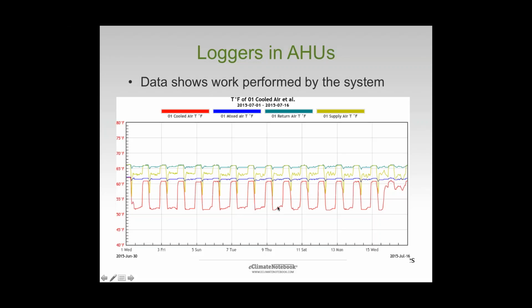Finally, after the air gets cooled down to this condition of 52 degrees, we send it out and it hits a heating coil. And before we send it out to the space, we find out that it's going to get heated back up to about, give or take, 64, 65 degrees. And at that point, we know what the supply air condition is that's going into the space. That tells us exactly what the air temperature is that we need in order to achieve our final set point condition out where the collection is stored or out in the public area. So being able to follow those paths and think about what each of those plots means, and how much work is being done from one step to the next in terms of how many degrees is happening, is a good way of beginning this diagnostic process and being able to think about whether or not we're operating as efficiently as we want to.